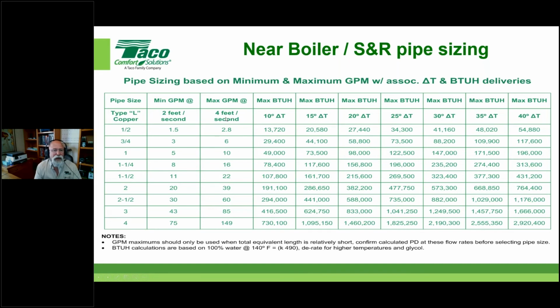So yeah, that's all this slide does. It just reminds you, if we stay between 2 feet and 4 feet per second, we're in the sweet spot, folks. You'll stay out of trouble. Again, it has to apply to the pipe and type that you're using, but it keeps you out of trouble.